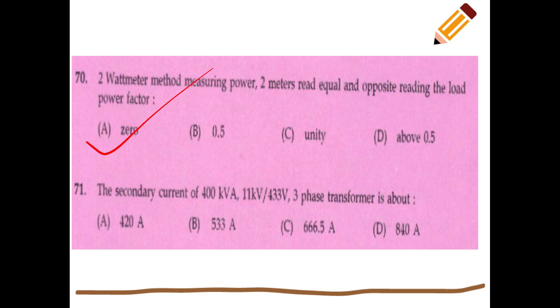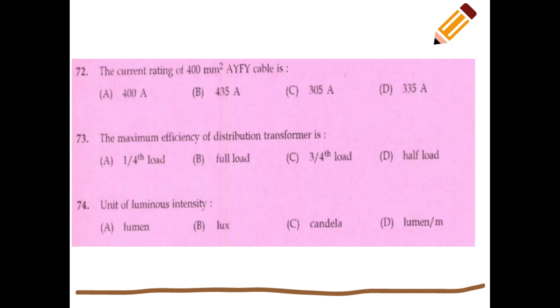The secondary current of a 400 kVA, 11 kV to 433 V three-phase transformer: using V1/V2 = I2/I1, the answer is 533 A.